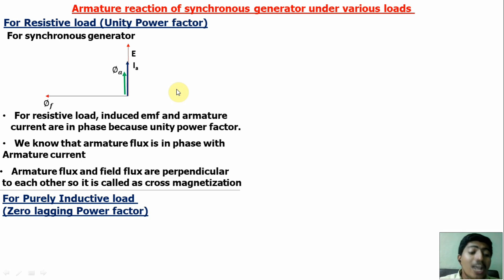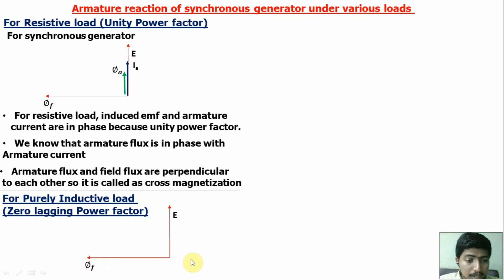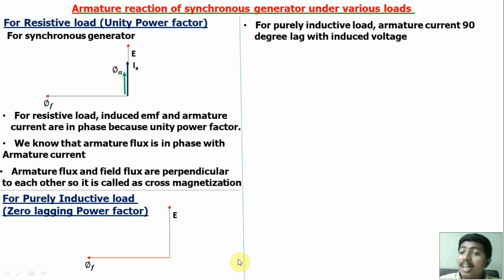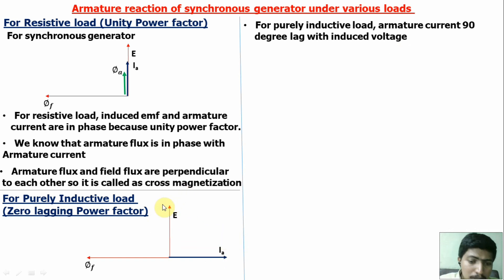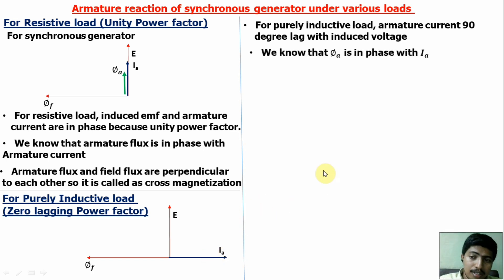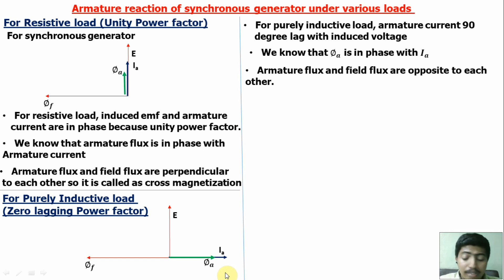For a purely inductive load — zero lagging power factor — the phase angle between induced EMF and field flux is 90 degrees. For a purely inductive load, armature current lags the induced voltage by 90 degrees. Since armature flux is in phase with armature current, the field flux and armature flux are opposite to each other. The resultant flux will be decreased, so this effect is called demagnetization.